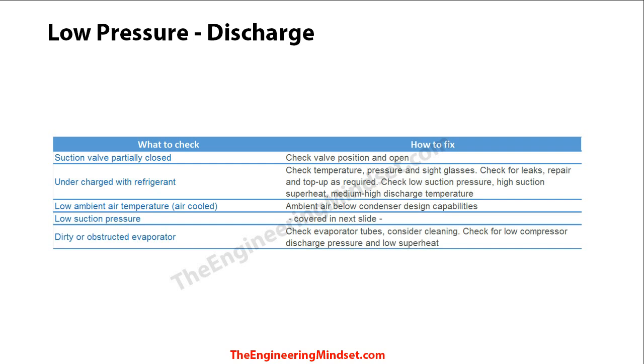Another cause of low discharge pressure is ambient air temperature being too low — air-cooled chillers cannot operate in those conditions, and you'll need to reprogram the system, checking with the manufacturer first. This can also result from a low suction pressure, which we'll cover next, and the most common cause on this list is a dirty or obstructed evaporator. Check the evaporator tubes and clean them to ensure maximum heat transfer.